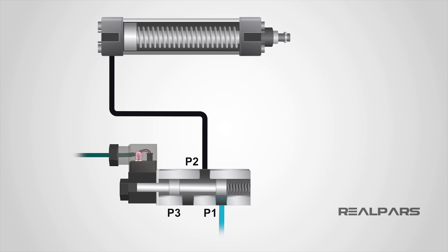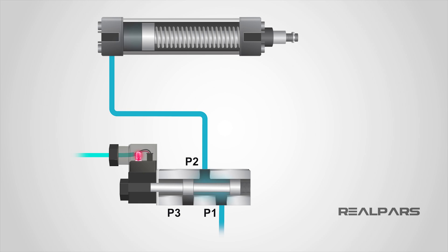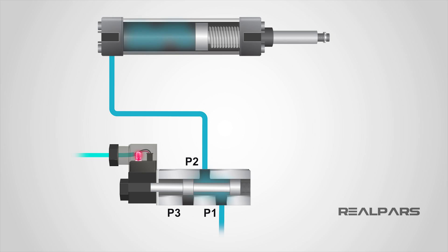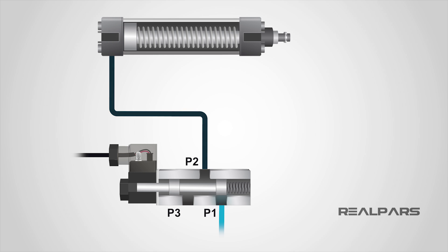Now imagine we operate the actuator. We would see the spool change position and the cylinder extend. This is because the spool has moved position, unblocking port 1 and simultaneously blocking port 3, resulting in allowing airflow from port 1 to port 2 while blocking the exhaust. This is known as our working position. The cylinder will remain extended until the spool is moved back to the normal position, either by way of another actuator at the opposite end of the valve, or by an internal spring return.